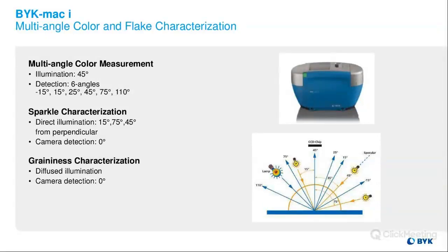Yeah, 5,000 readings, whether they're standards or samples. And that's just holding those readings on the instrument, right? So you can download those to the software, wipe the instrument clean, and you're still protecting that data in the software. Is that right? Yes, there is no limit to how much data you can store in the software. Oh, it's a billion. That's what I was thinking. Oh, right. Okay. Yeah, of course.